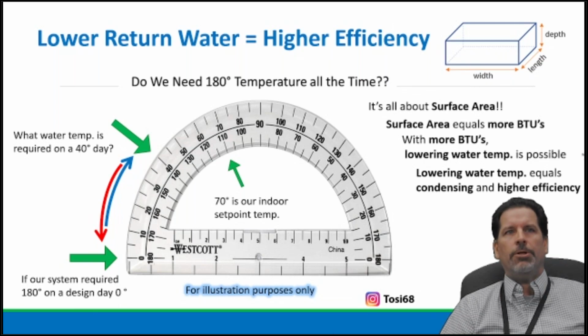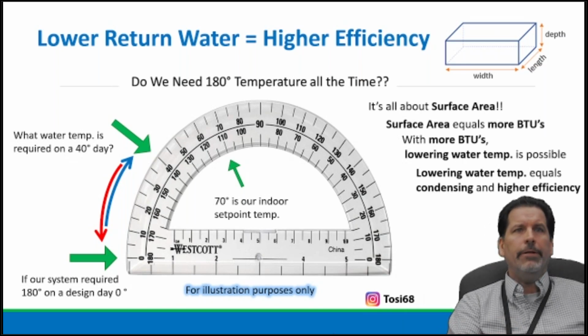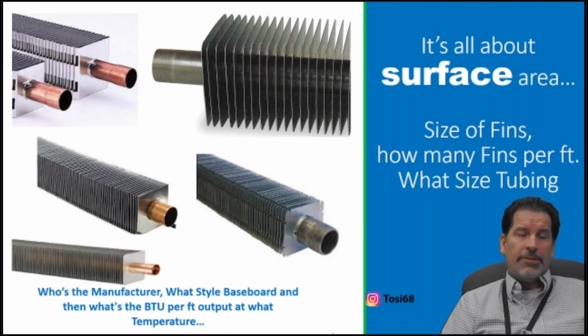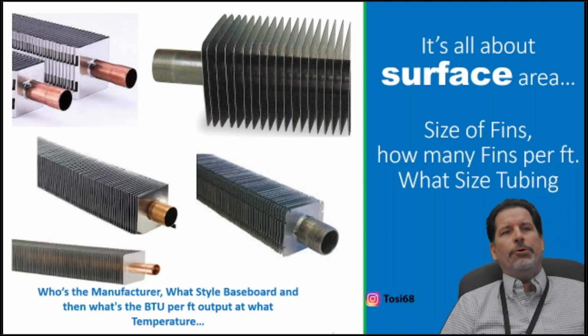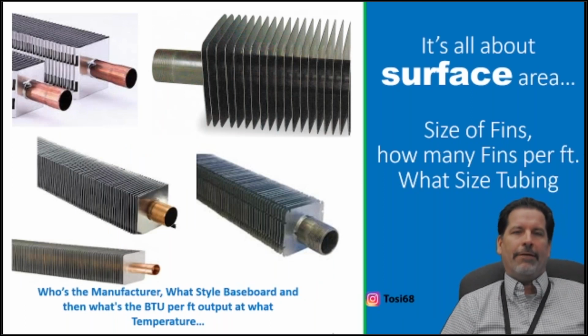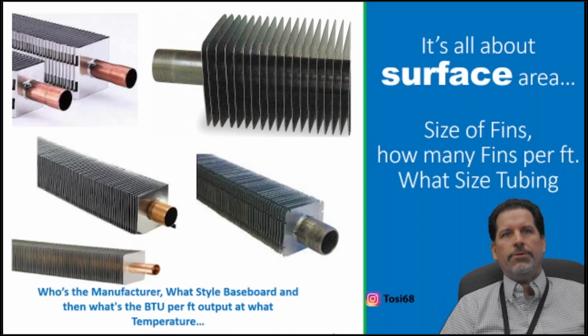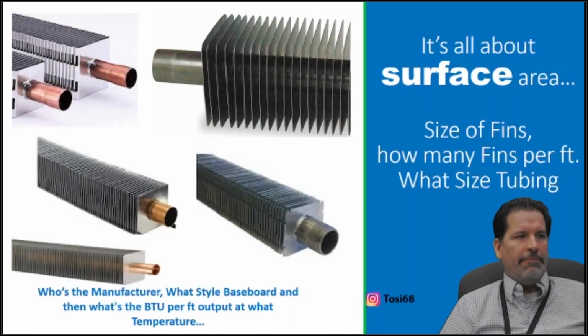And it really can show its ugly face, especially on the efficiency side, costing very high dollars for fuel just to run it on a lower outdoor temperature day. So anyway, here you go, surface area. I can't say it enough. If you have more surface area, you have more ability to lower water temperature. Bottom line, take advantage of doing this, taking advantage of 50 years of oversizing.